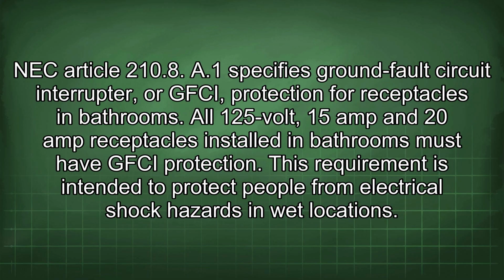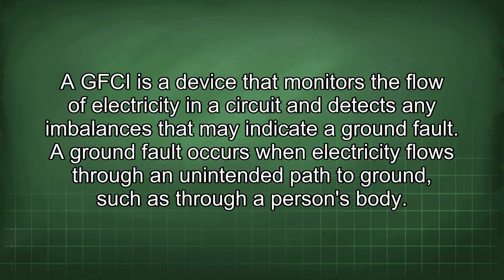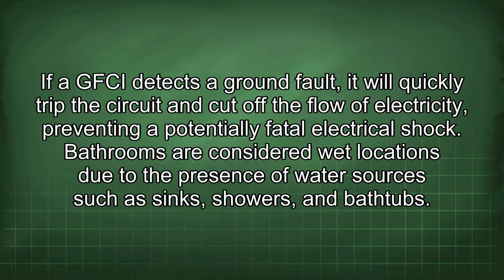electrical capacity. NEC Article 210.8(A)(1) specifies ground fault circuit interrupter, or GFCI, protection for receptacles in bathrooms. All 125-volt, 15-amp and 20-amp receptacles installed in bathrooms must have GFCI protection. This requirement is intended to protect people from electrical shock hazards in wet locations. A GFCI is a device that monitors the flow of electricity in a circuit and detects any imbalances that may indicate a ground fault. A ground fault occurs when electricity flows through an unintended path to ground, such as through a person's body. If a GFCI detects a ground fault, it will quickly trip the circuit and cut off the flow of electricity, preventing a potentially fatal electrical shock.